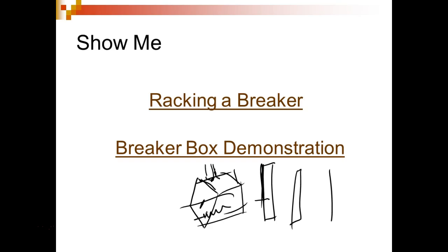That's where you put it. What do you think may have gone wrong? Well, they didn't have things right, or they were putting in too much pressure and the flaps got bent over, or there was a short out there on the line. It wasn't the breaker's fault. So the breaker kicked and burned up, some parts got burned up in it, and they came back and fixed it. But when they put it back in, that short was still out there in the system. As soon as it came on and those rails touched, it created an arc and it blew up.